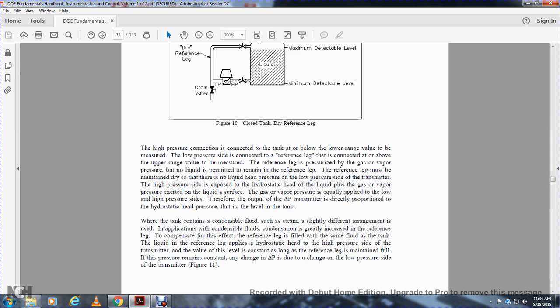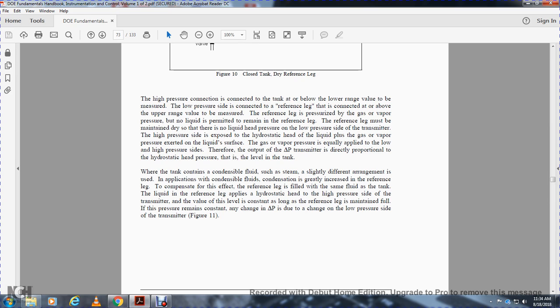Therefore, the output of the differential pressure transmitter is directly proportional to the hydrostatic pressure, and therefore to the level in the tank. With a tank containing condensable fluids, you will see a slightly different arrangement in the application. Condensable fluids and condensation greatly increase, so to compensate for the effect the reference leg is filled with the same fluid. The tank liquid in the reference leg applies the hydrostatic head to the high pressure side of the transmitter, so the level value is consistent as long as the reference leg is maintained full.